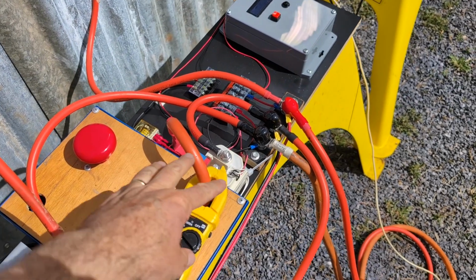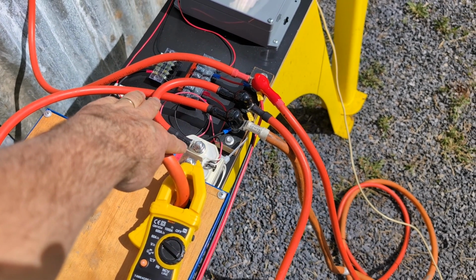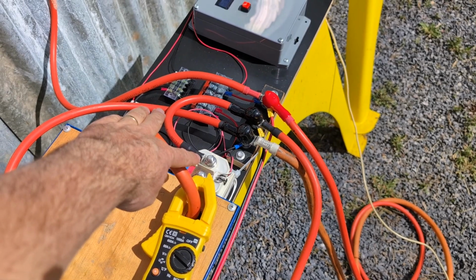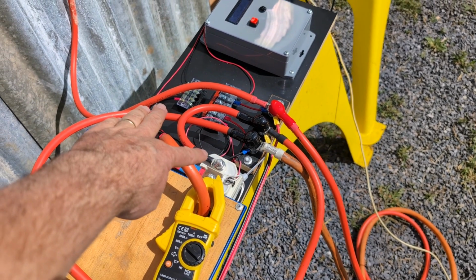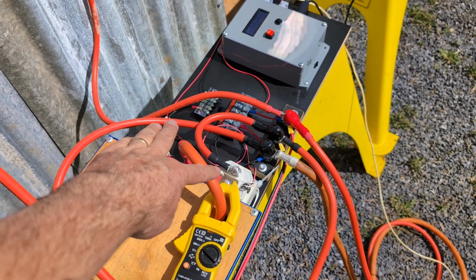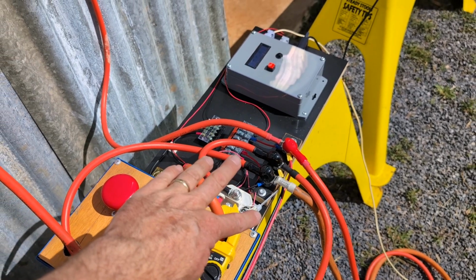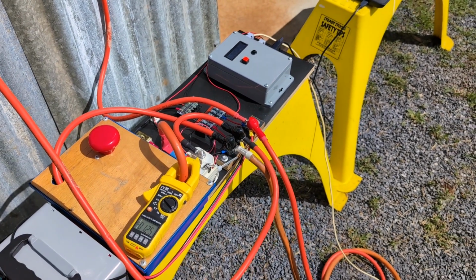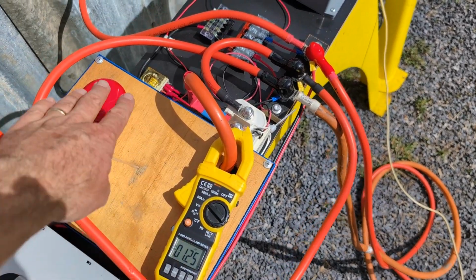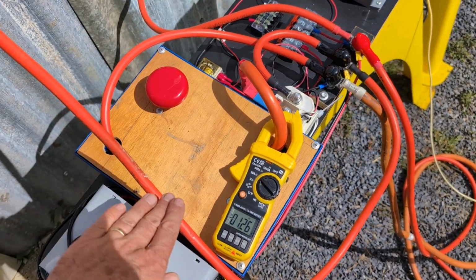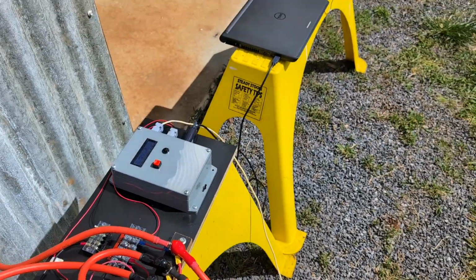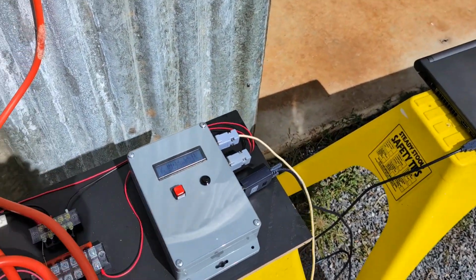So when that BMS was first powered, it turned the contactor off. It must have come on to start with - I heard it click twice. So it must have come on, then turned off while it was starting up, and then turned back on again. So it thinks everything's happy now. The contactor is on, but I don't have my isolator on here. So let's just see what the BMS is telling us.